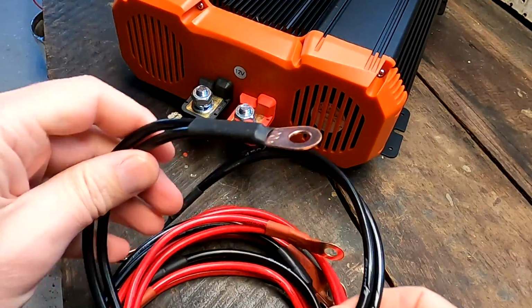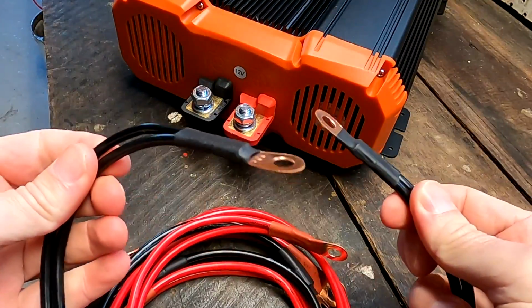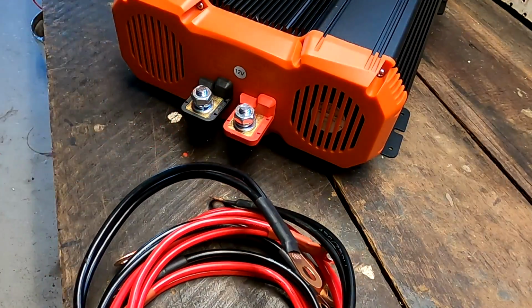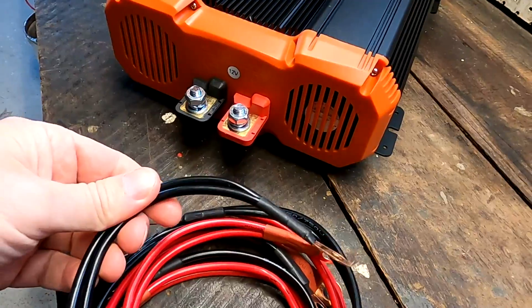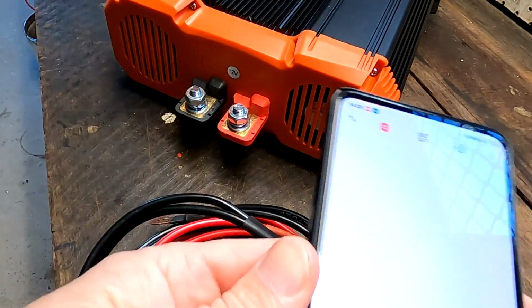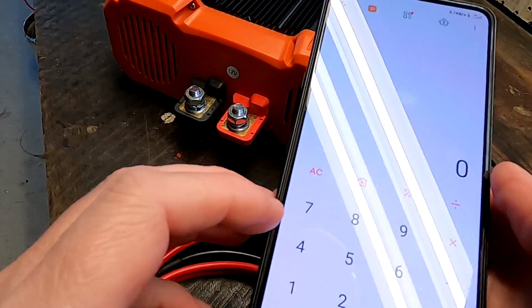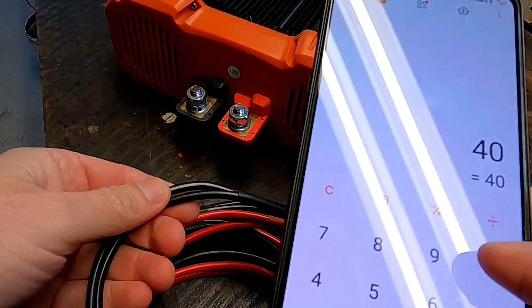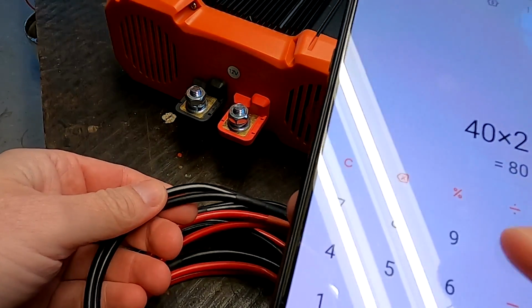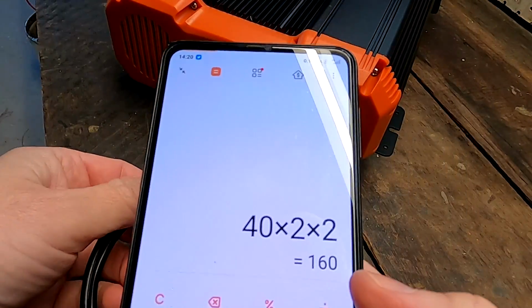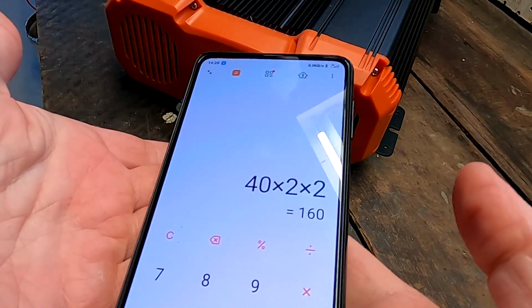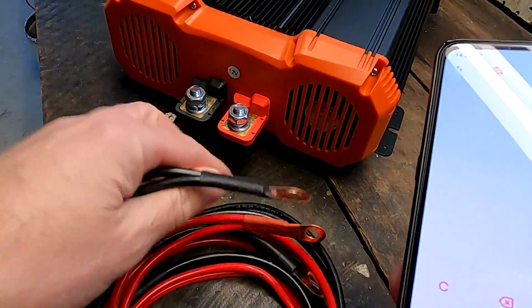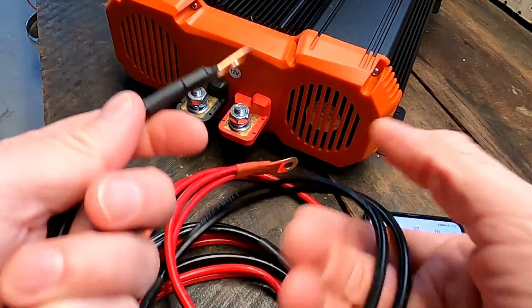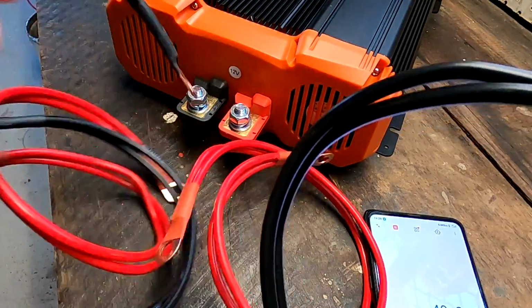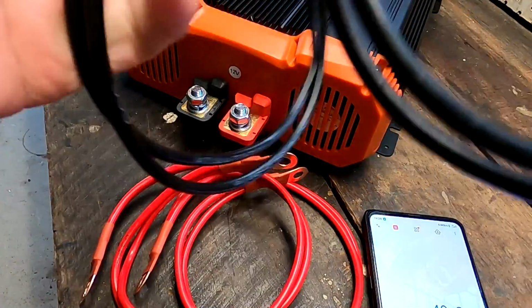Okay, so before we connect these cables here to the inverter, I just want to make some quick calculations. So this is a 6mm cable - 6mm is good for 40 amps constant current, times 2 and times 2, so that's 160, that was easy, didn't need a calculator for that.